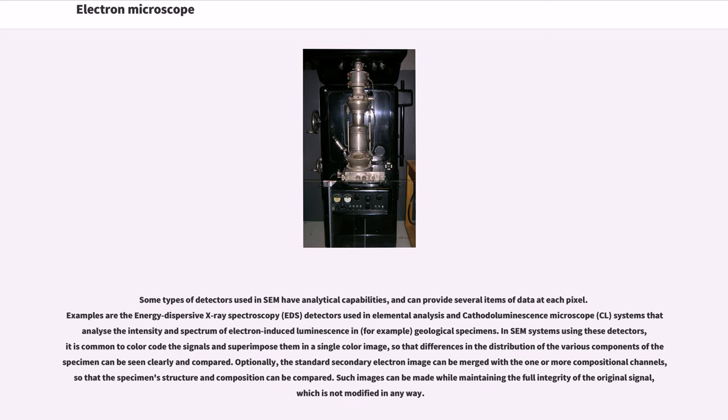Some types of detectors used in SEM have analytical capabilities, and can provide several items of data at each pixel. Examples are the energy dispersive X-ray spectroscopy EDS detectors used in elemental analysis and cathodoluminescence microscopy CL systems that analyze the intensity and spectrum of electron induced luminescence in, for example, geological specimens. In SEM systems using these detectors, it is common to color code the signals and superimpose them in a single color image, so that differences in the distribution of the various components of the specimen can be seen clearly and compared.